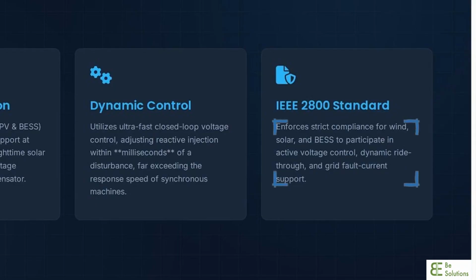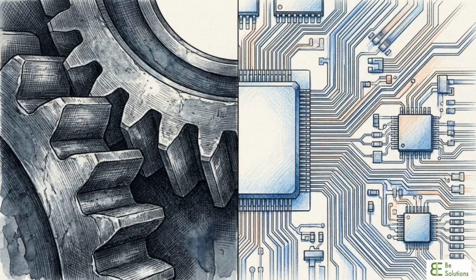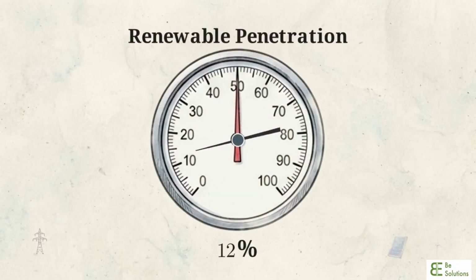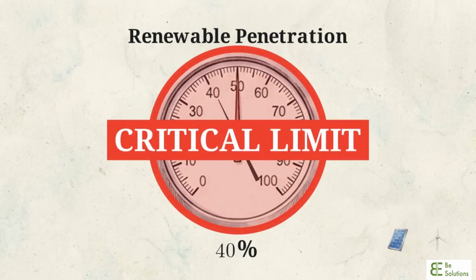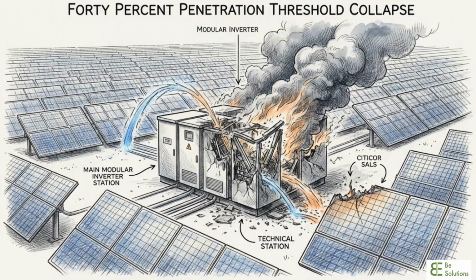Utility-scale solar and battery systems are legally required to actively control voltage profiles, endure dynamic ride-through scenarios without tripping offline, and provide immediate grid fault current support. Digital programming now dictates the stability circuits once provided by spinning rotors. As legacy plants retire, modern networks approach a critical bottleneck, the 40% penetration threshold. Once inverter-based resources make up more than 40% of the total grid mix, standard operational technology begins to fail.